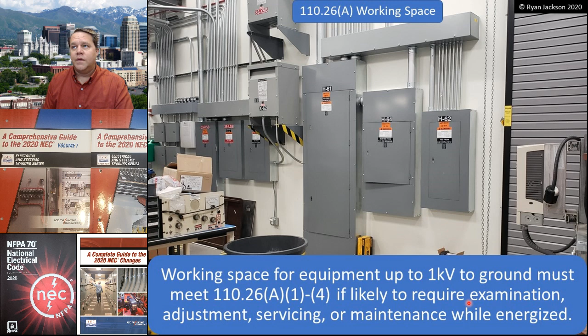So in this photograph, we need to have 3 feet of depth, we need to have the full width of the equipment, and the full height of the equipment, because it appears the equipment is taller than 6.5 feet. So if you could visualize an empty refrigerator box, I need to be able to take a refrigerator box and stick it in front of the switchboard, and nothing can be in that area except for you, the electrician. The other thing that can be in there besides you, however, is other electrical equipment.